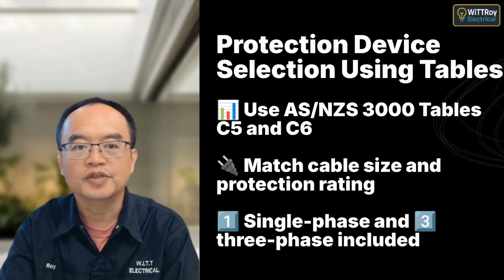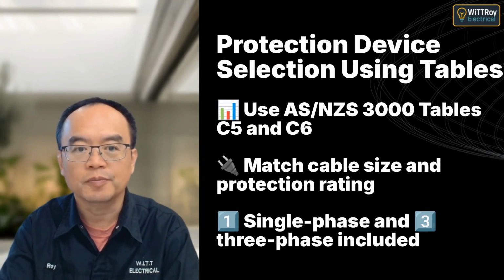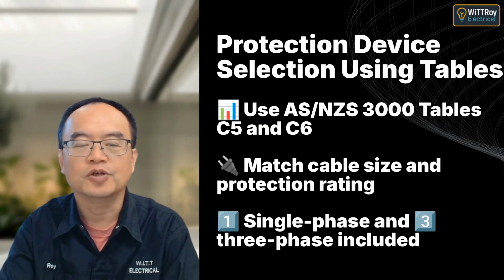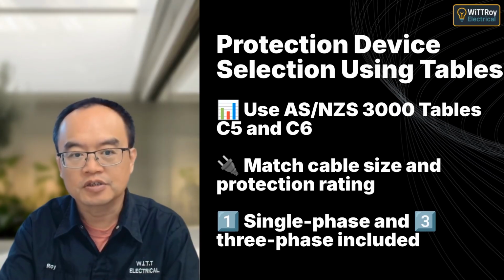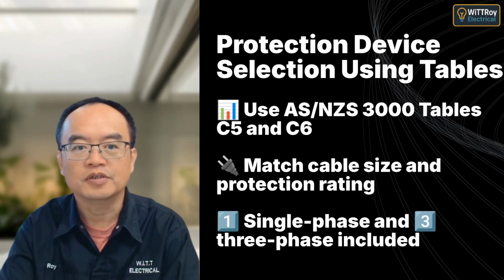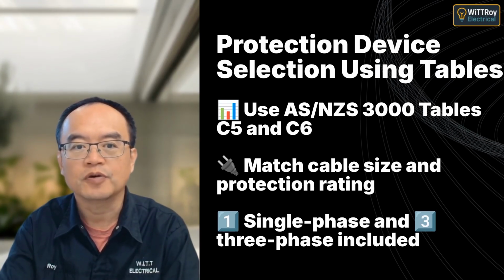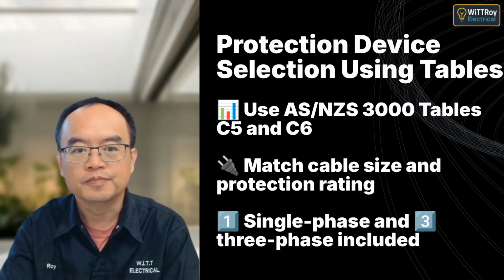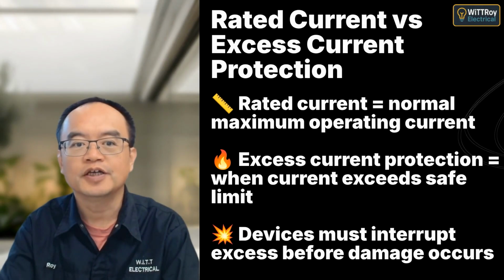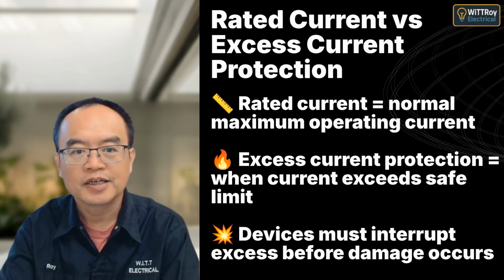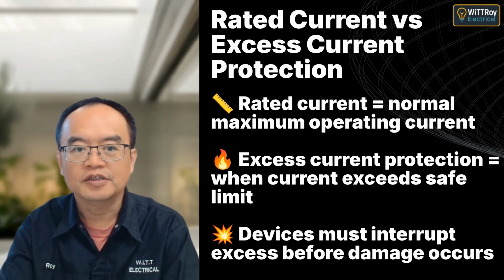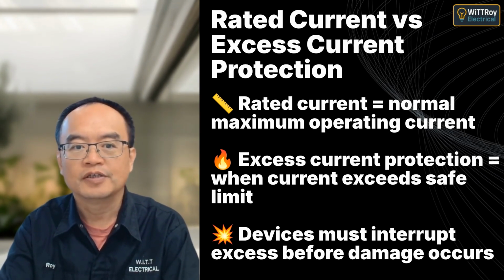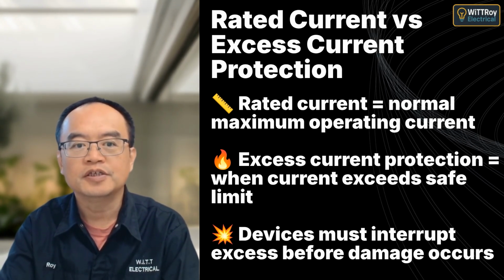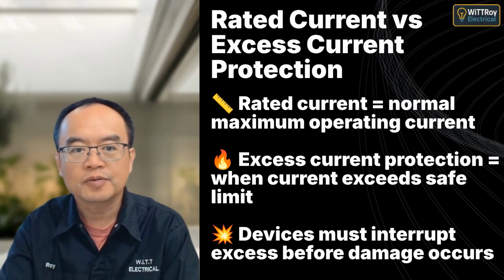To choose protection devices correctly, use the tables in Appendix C of AS/NZS 3000. These match conductor sizes to suitable device ratings under various conditions for both single-phase and three-phase systems. Rated current is the maximum load a device can carry continuously. Excess current protection ensures the device interrupts the supply when current exceeds that limit, helping to prevent damage or fire.